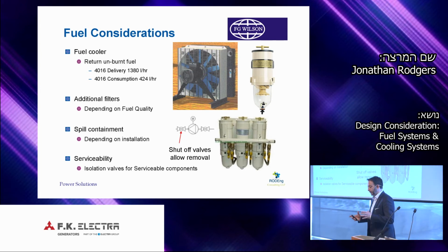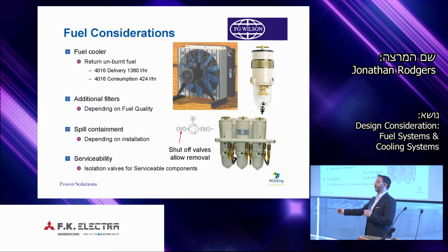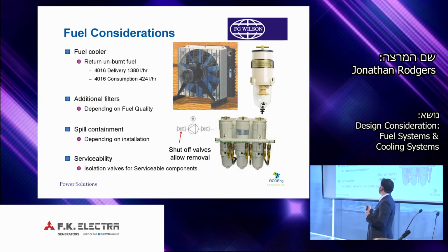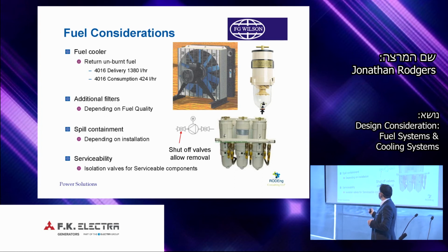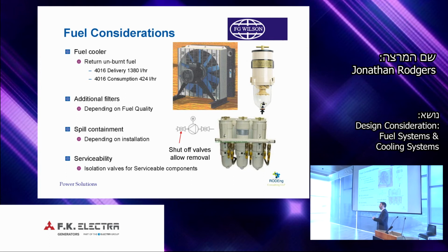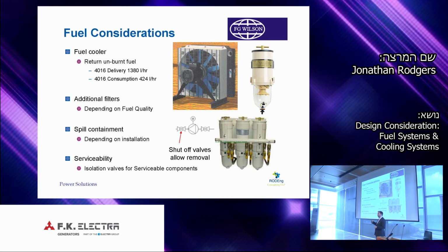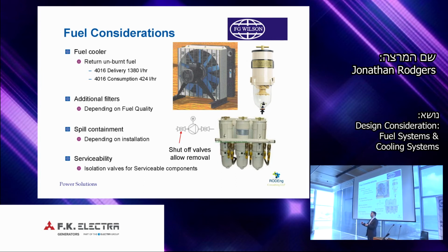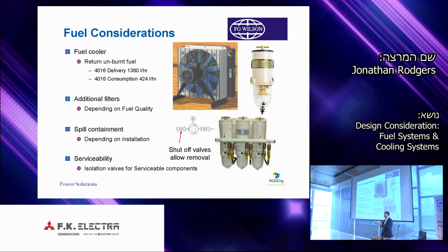So other points that are important in our system, I mentioned all of our engines will have a fuel return as well as fuel supply. That fuel, this example is 4016 at 2000 kVA. The engine will be consuming 424 litres per hour, but the pump on the engine is gear driven, so it always flows at the same speed, matched to the rotation of the flywheel. So we're looking at a 1500 RPM pump. When it's on zero load and when it's on full load, it always has the same flow. So that flow through the engine will be 1,380 litres per hour. At maximum load, the engine will only use a third of that, 424.